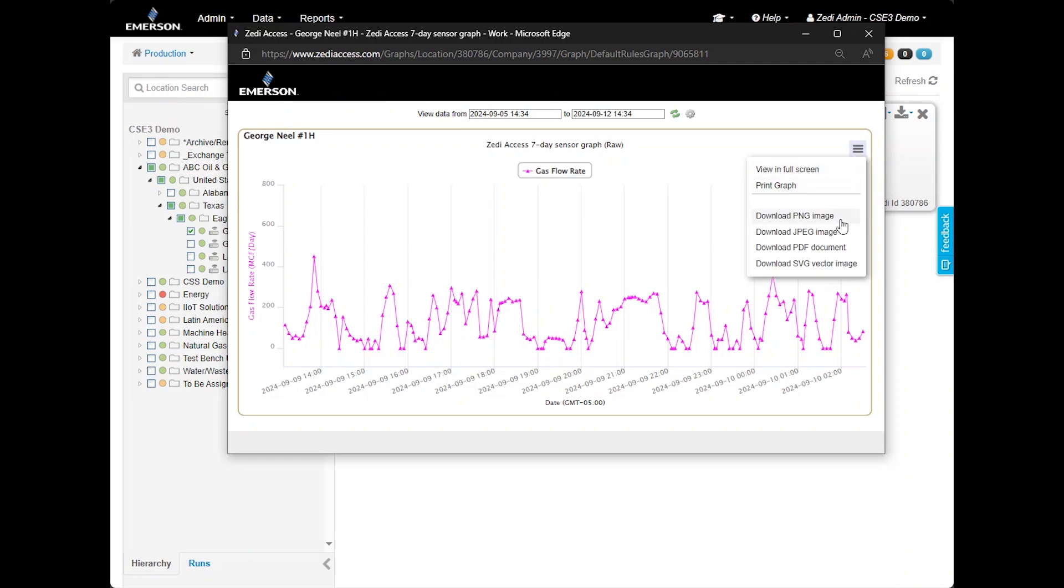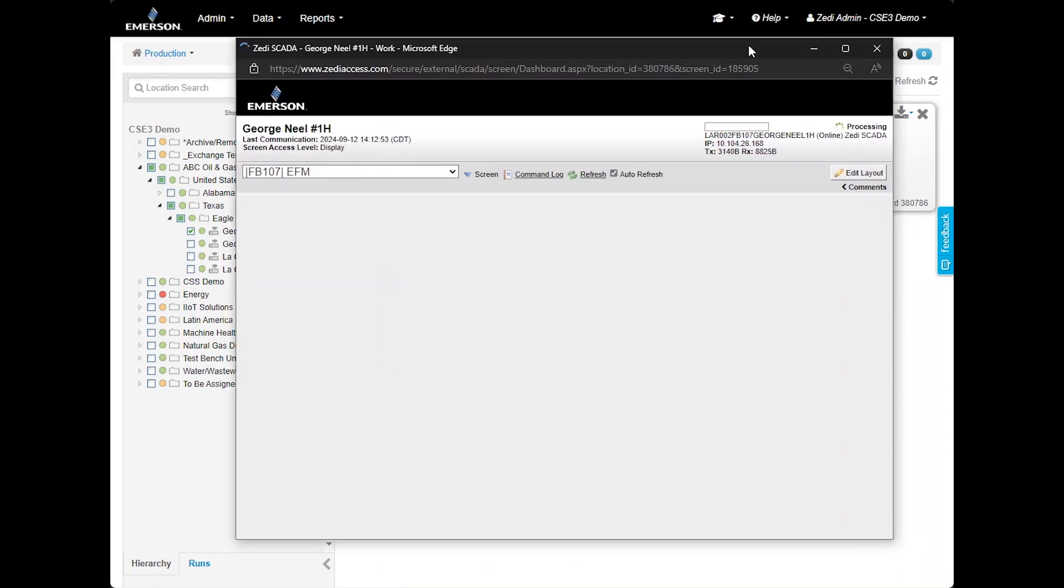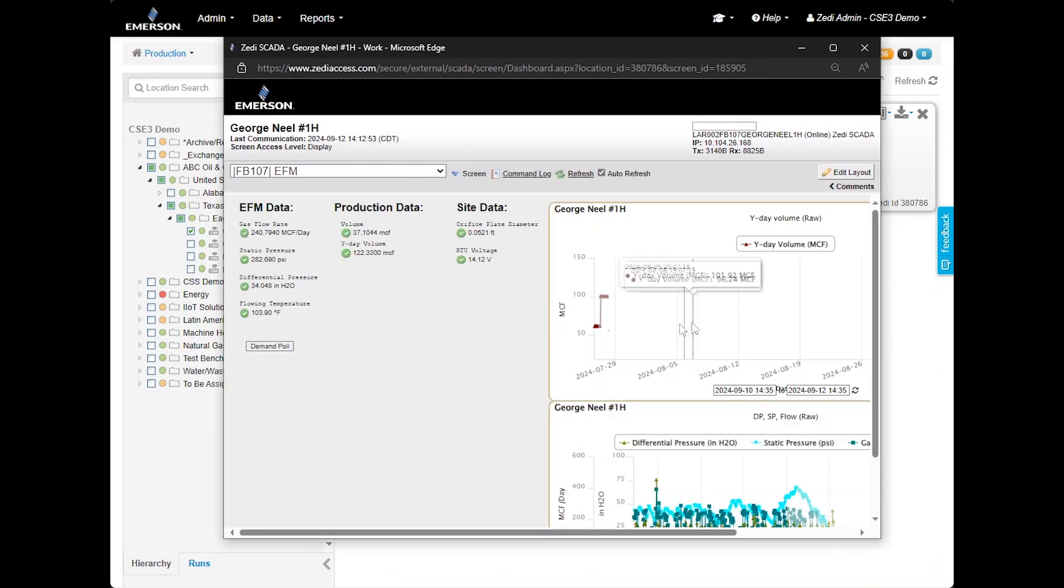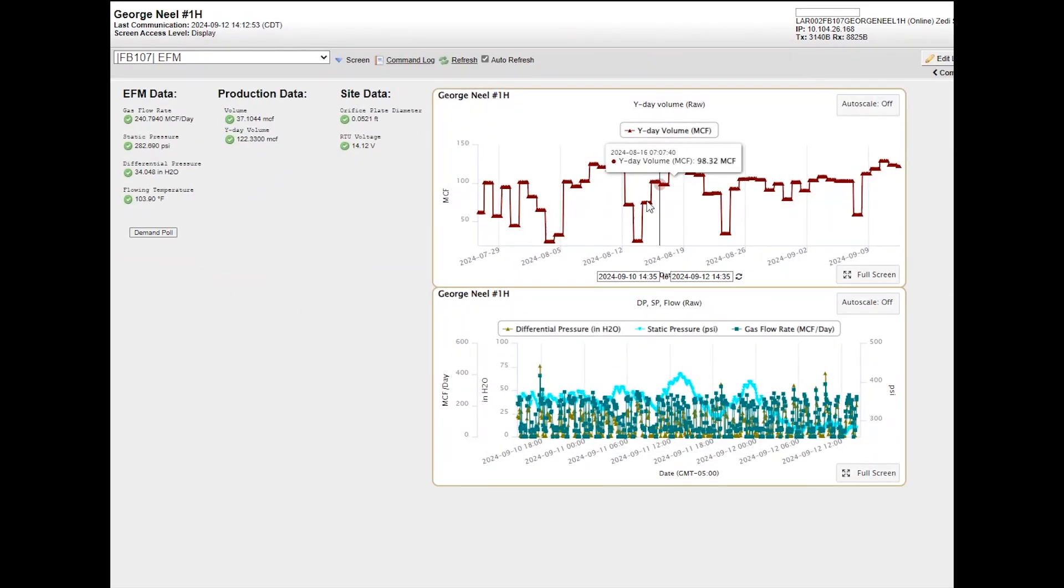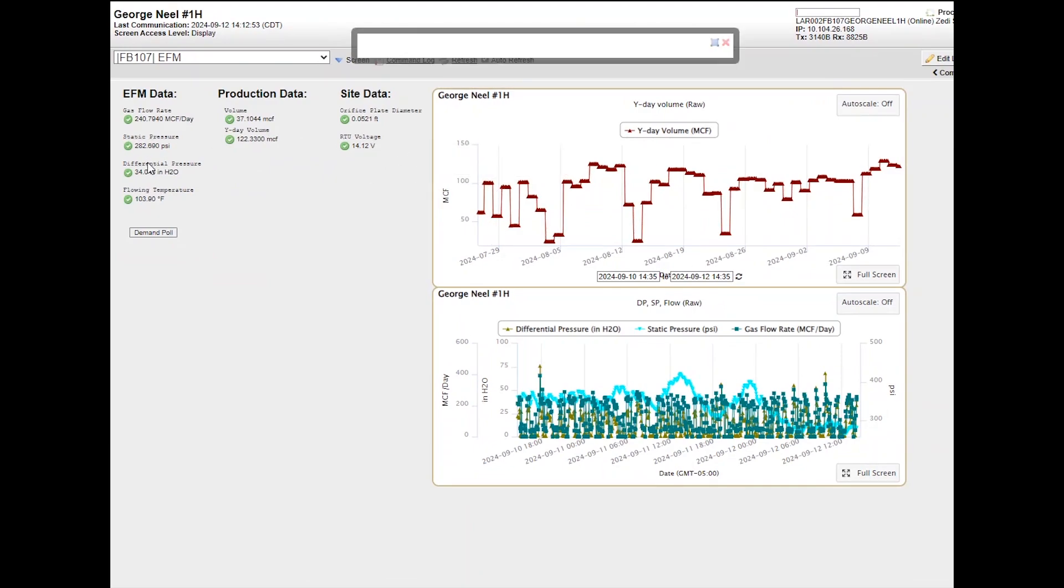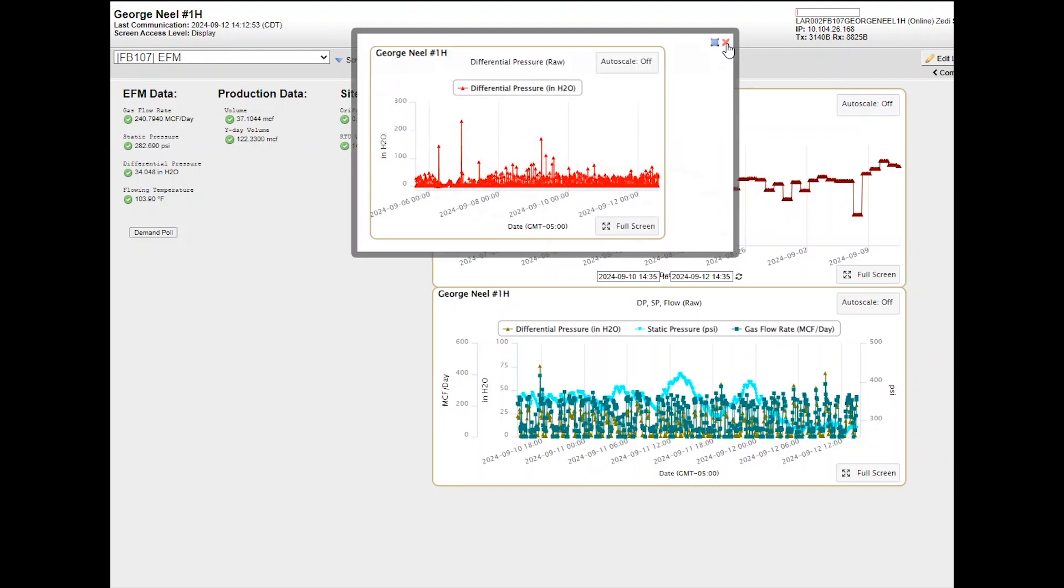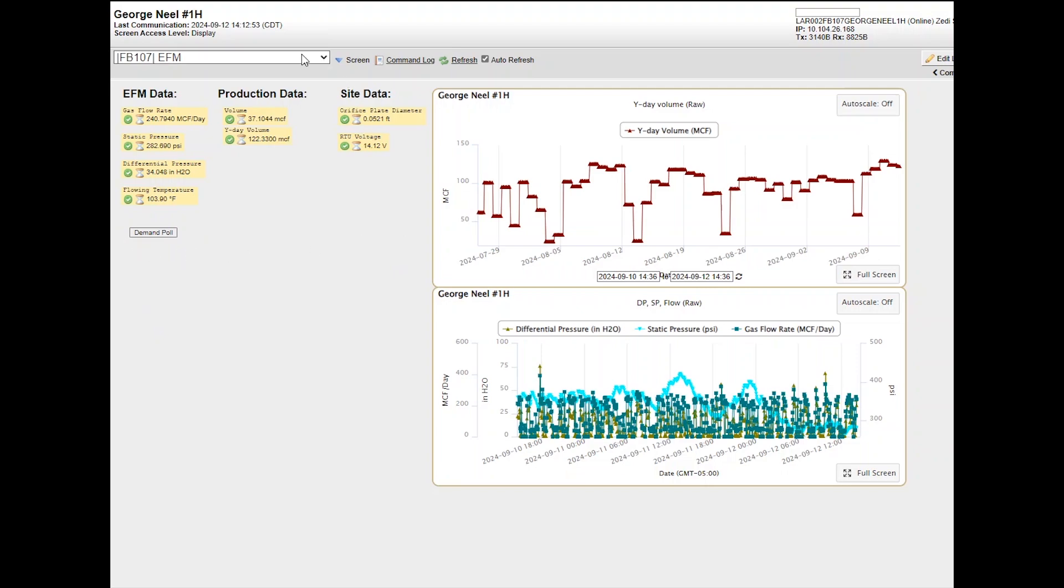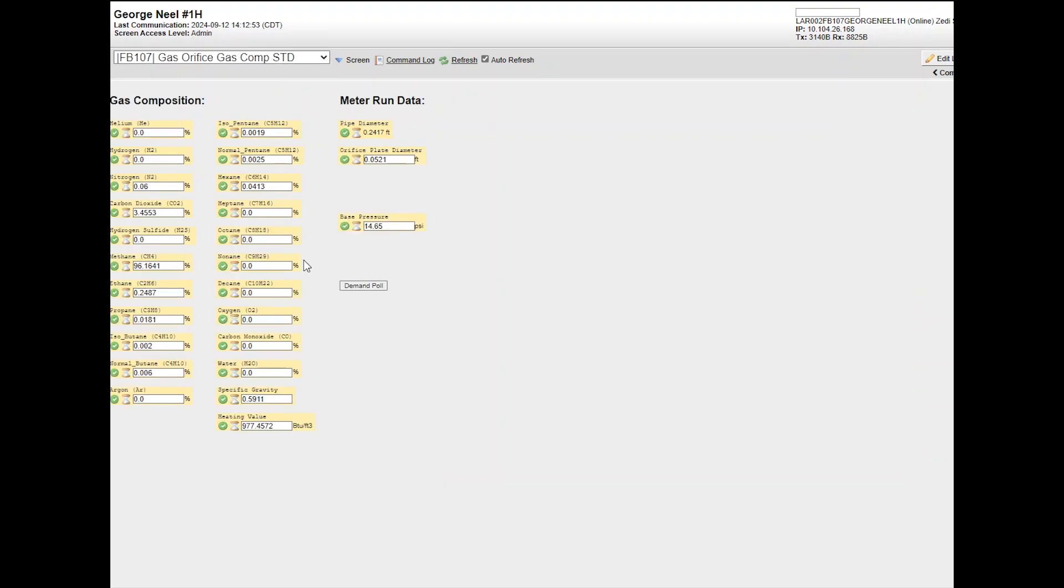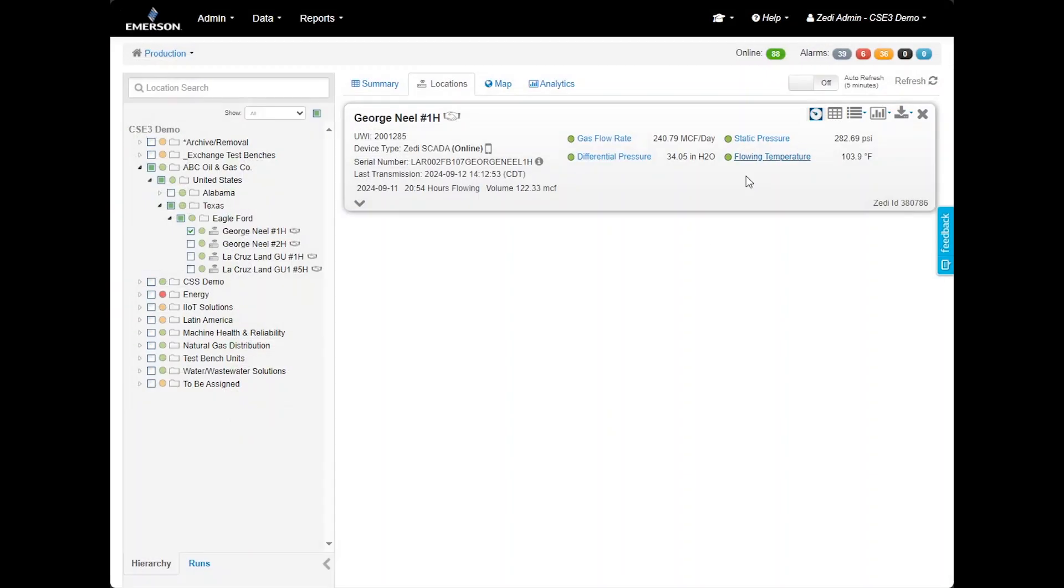To view and control your devices, from the site display, select the live data screen by clicking on the clock icon. This screen allows users to control the device, if applicable, and access additional data. You can input device values directly and view sensor data. Each sensor also offers 7-day trend data when selected. There is also a demand pull button that retrieves the latest data from the device and updates our cloud-based system. Note that there is no extra charge for using the demand pull feature. Users can adjust gas compositions and orifice plate settings. These changes are immediately applied to the device on site. Devices will refresh automatically based on your polling frequency, but users can use the demand pull and refresh data as frequently as needed.